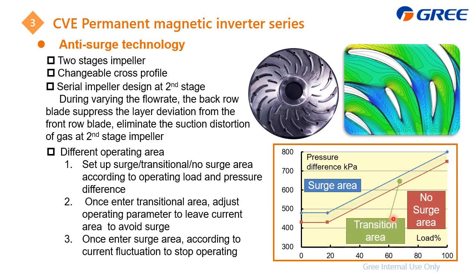So if this compressor is during operation in this no surge area, it is completely okay. We will not do anything about it. And if it gets into this green line, green area zone, we need to adjust the parameter, just like increase the compressor RPM to ensure it will leave this zone. This is to ensure it will not enter the surge area.